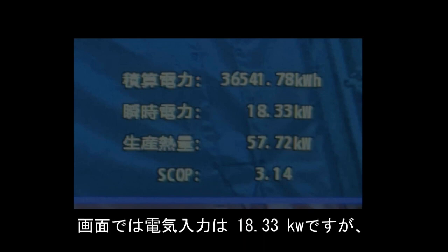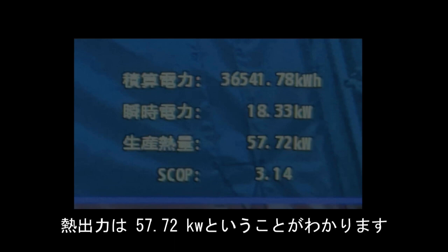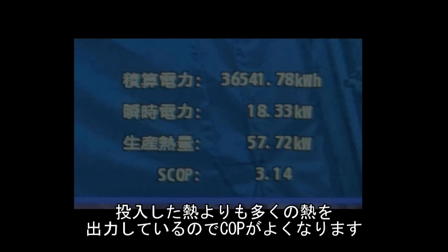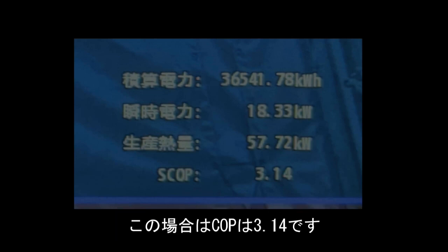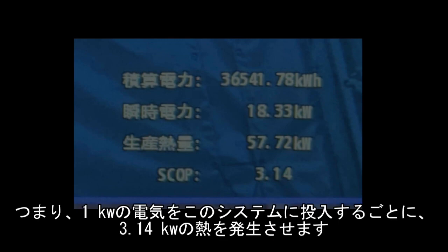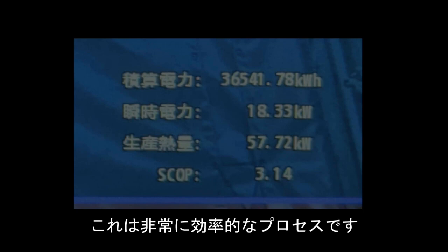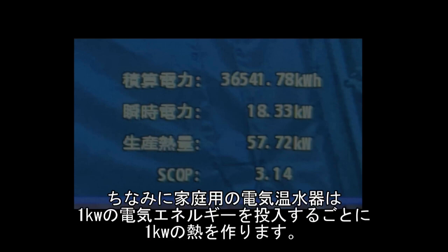In this picture you can see our electrical input is 18.33 kilowatts. However, our heat output is 57.72 kilowatts. Because we are transferring the heat rather than creating the heat, we get a coefficient of performance, in this case 3.14. So for every kilowatt of electricity we put into this system, we transfer 3.14 kilowatts of heat. This is a very efficient process, as you can see. For example, your household kettle will give you 1 kilowatt of heat for every 1 kilowatt of electrical energy you input.